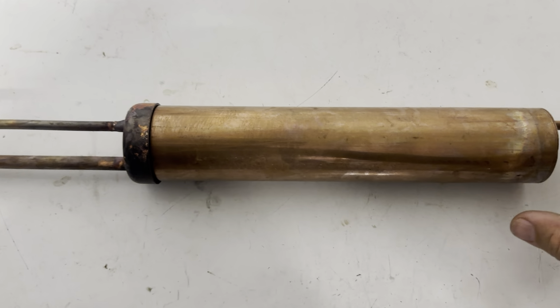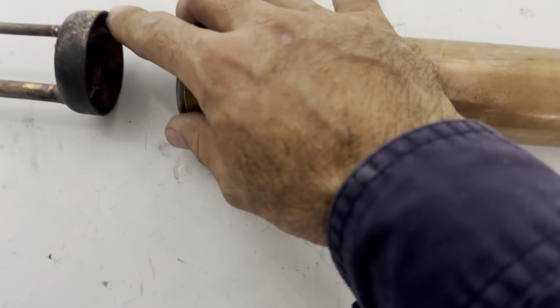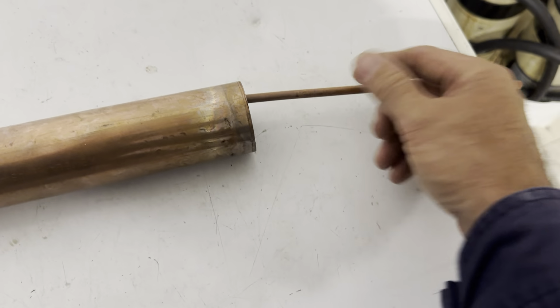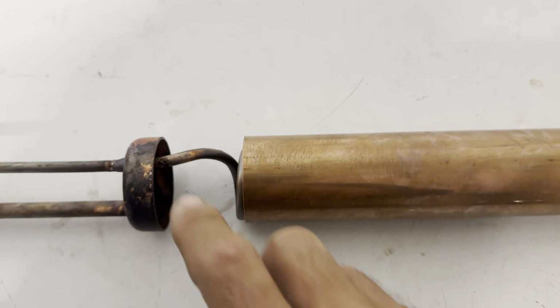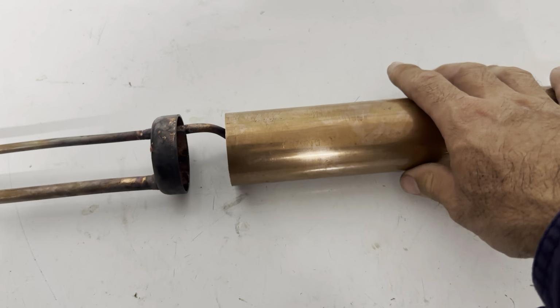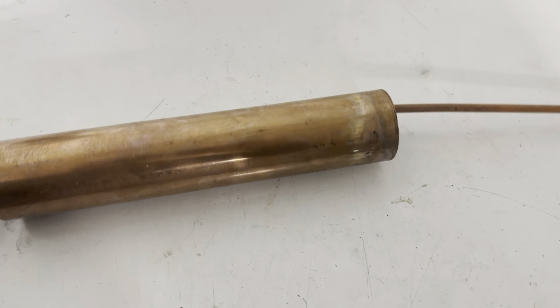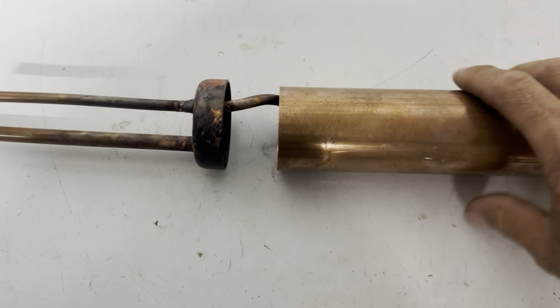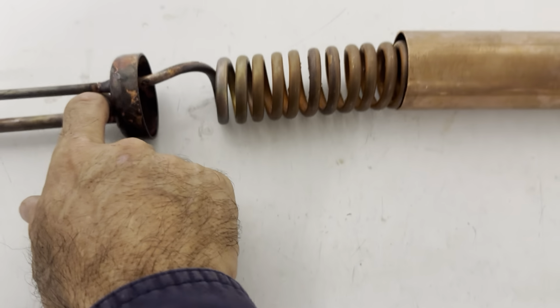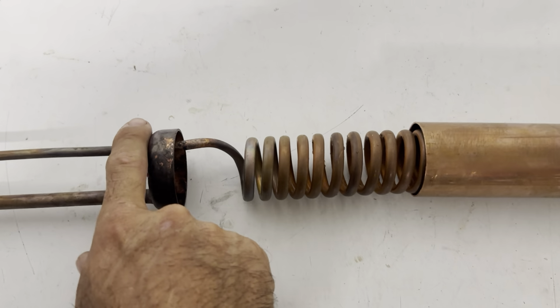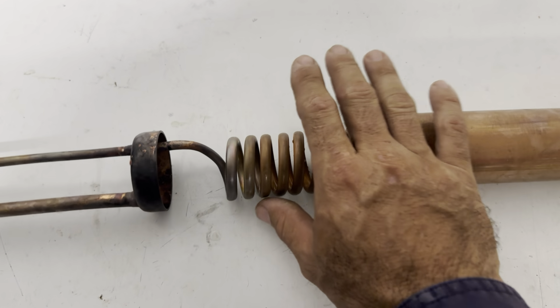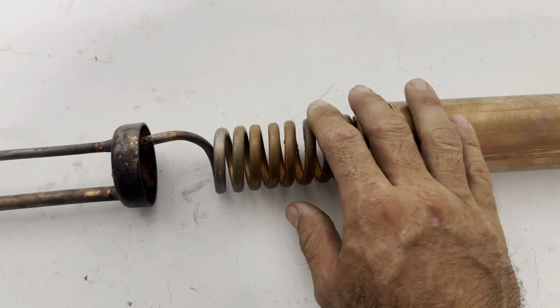With this slid on like that, so this is open cavity here, you'll have the suction gas coming back the other way. So the advantage of doing this is that basically you get a heat exchange effect between the suction and the liquid sides of the system.